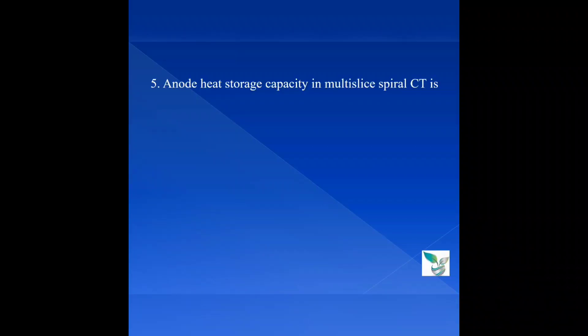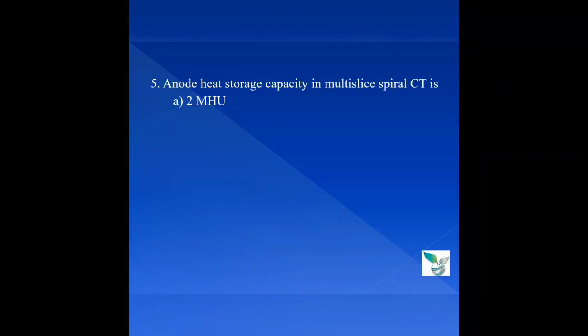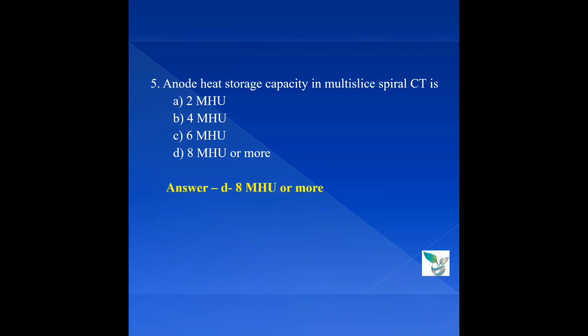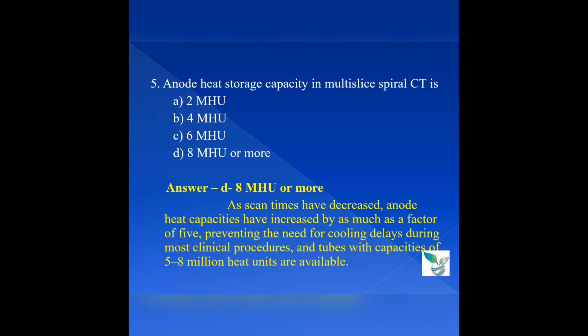Question 5: The anode heat storage capacity in multi-slice spiral CT is — Option A: 2 MHU (Mega Heat Units), Option B: 4 MHU, Option C: 6 MHU, Option D: 8 MHU or more. The answer is Option D: 8 MHU or more. As scan times have decreased in spiral CT with continuous motion of the X-ray tube and detector, the anode heat capacity has increased by as much as a factor of 5, and tubes with capacities of 5 to 8 million heat units are available.